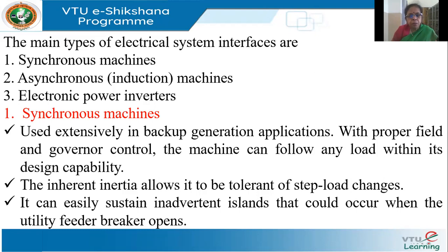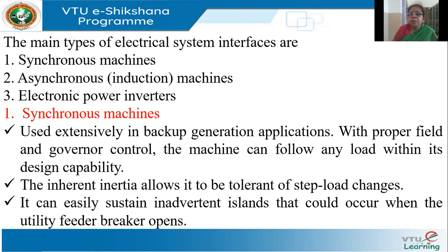Synchronous machines are alternators, and they have to be synchronized. Alternators are excited by DC — you have DC excitation for the field and the alternator voltage is brought up to the grid voltage and synchronized at the point of interface. In a synchronous machine, it's a constant speed machine. The field controls the voltage level and the governor of the prime mover controls the speed and hence the frequency. By controlling the field and the governor, we can make the machine follow any load change within its design capability.